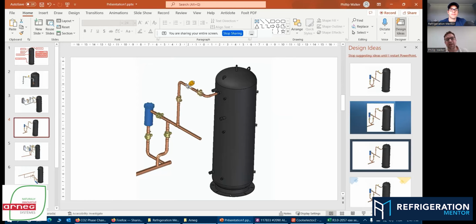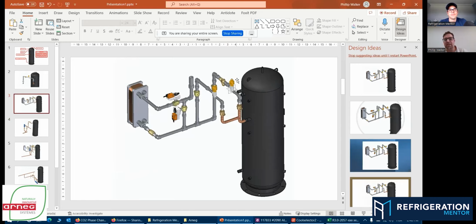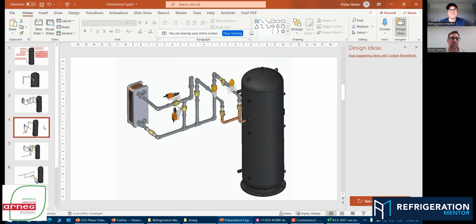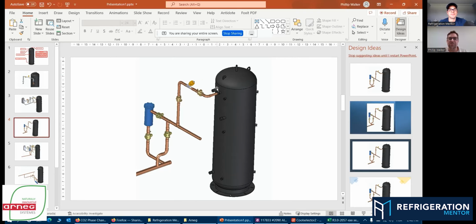So as you can see here, the flash gas, here we're going down, and then here is the suction manifold for the medium temperature compressors. The gas here isn't being thrown 100% into that suction manifold. The quantity of gas is being controlled, because the design right here is we're going to maintain a certain quantity of flash gas in the tank to maintain pressure within the head of the tank, this part on the top here. So this valve is working complementary to this high pressure expansion valve right here. And on this vertical flash tank, you really need the 2 of them. You need a valve to regulate as a high pressure expansion device to form liquid inside this flash tank. And you also need the complementary valve here on the flash gas outlet side, okay?